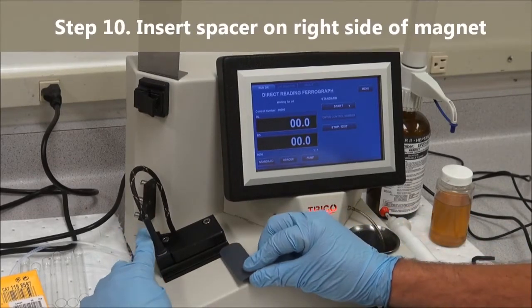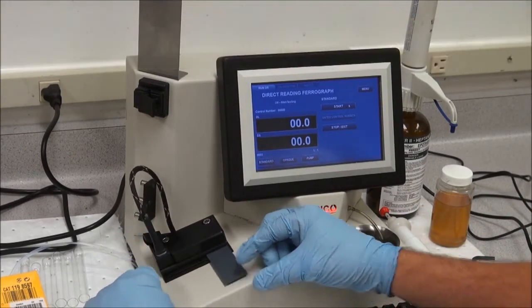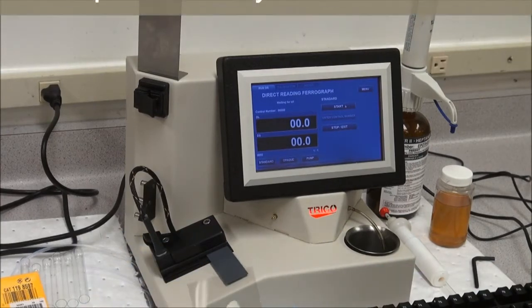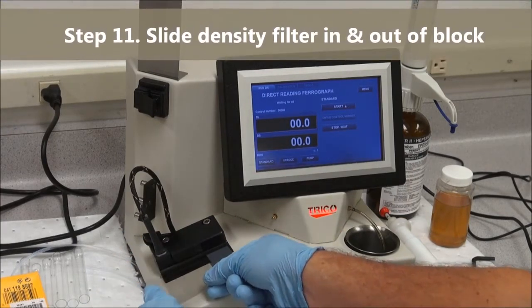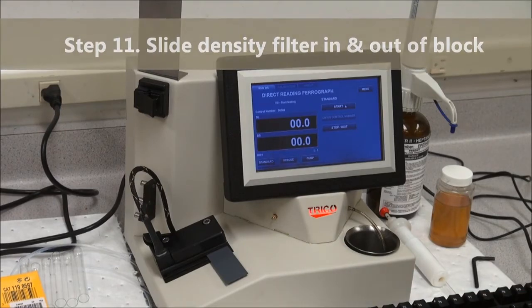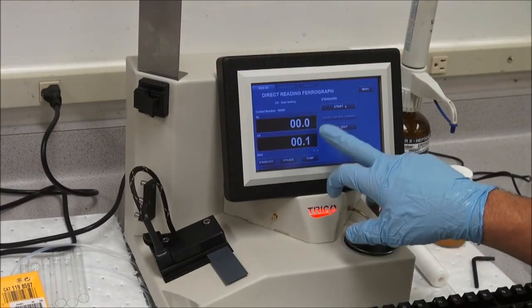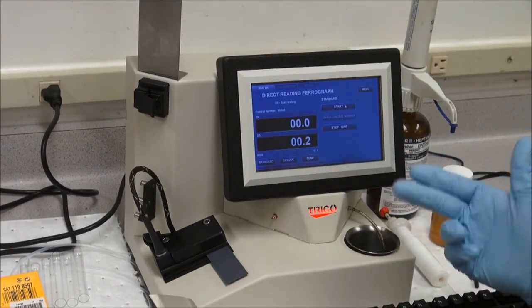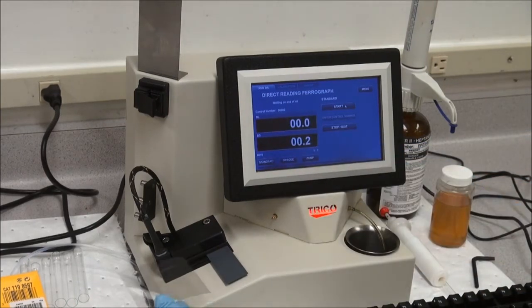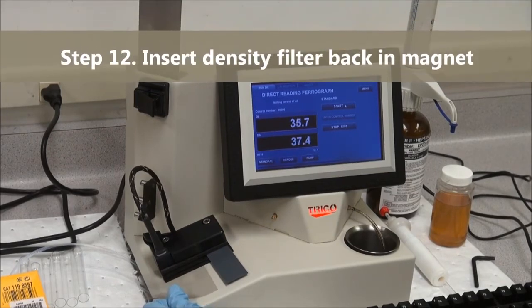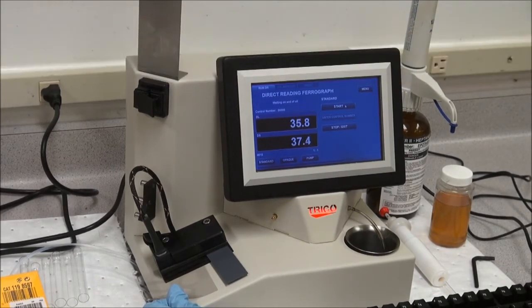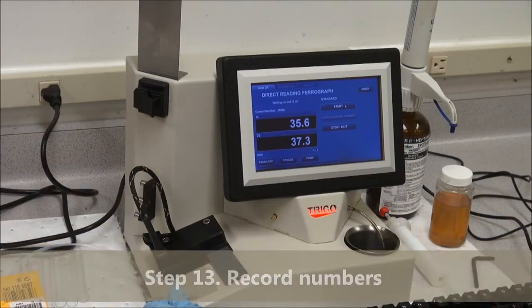Insert the spacer on the right-hand side of the magnetic block. Put the 0.1 density filter inside the block and pull it out immediately. The numbers will move up and down briefly, indicating that the oil is there. It'll say waiting on end of oil in the center of the screen. Insert the 0.1 density filter back into the block. Once the numbers have leveled out, these are your numbers, record them as necessary.